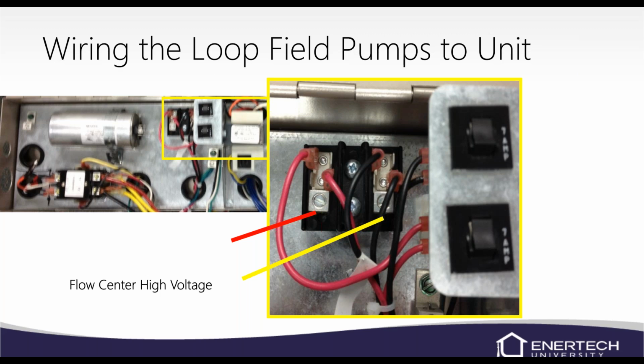So your desuperheater pump connects here, if you've got a desuperheater, as well as your flow center pumps. If you had a water-to-water unit, the load pumps will go there as well. So this is where your flow center pumps will be wired into. For some reason, if you hook them to a contactor, it's not the end of the world, because basically the power to this pump block comes directly from the contactor over through the fuses and then to the pump block.